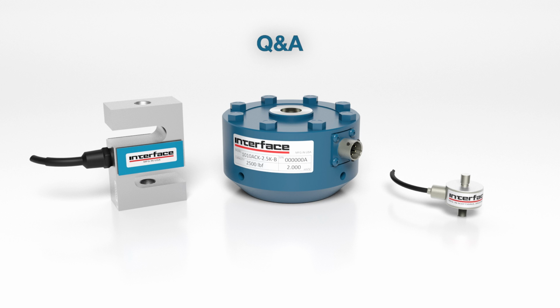From what I just heard, I would recommend a very robust sensor. Potentially, you could put that grab bar directly onto the load cell and pull directly on that. So I would recommend a low profile, potentially going up in capacity to make sure that it can take the potential side loads or axial loads. But in that case, it's tough to do something like that without introducing a parasitic load path, where you're trying to measure a direct load being applied only to that load cell. So that one's probably a good one to have that person call in and talk with one of our application engineers.